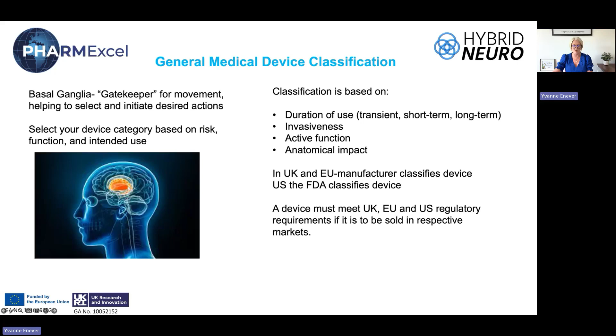So here in the UK, you can see the UK MDR versus the European MDR. The classification is very much around sets of rules, and those rules determine how your product is being used. And from those rules, you can then work out the classification. So for instance, to just give you an example, if you were looking at an implantable device, the rule that applies to that is rule 8 under the regulations, both in the UK and under the EU MDR. So you can go to rule 8 within the regulations and work through that rule, and it will then determine what the classification of your device looks like.